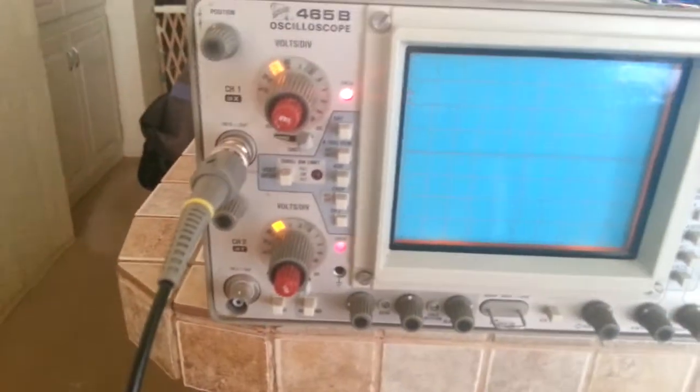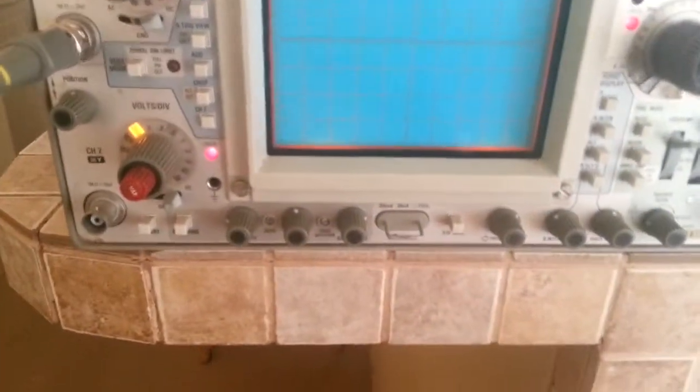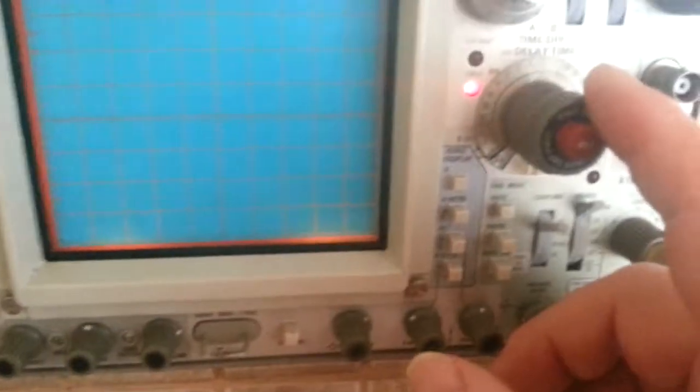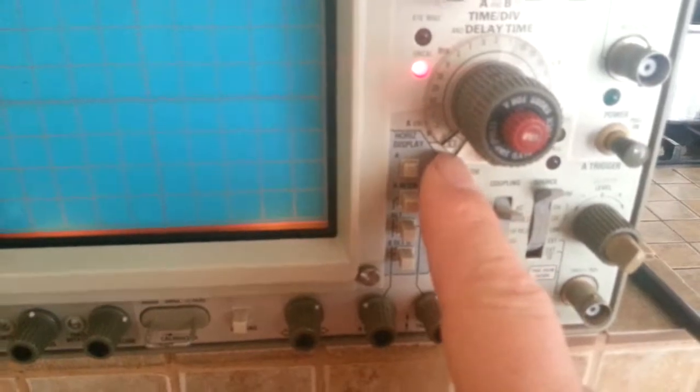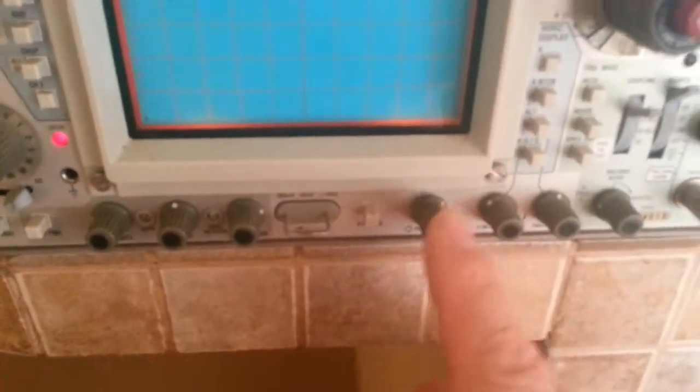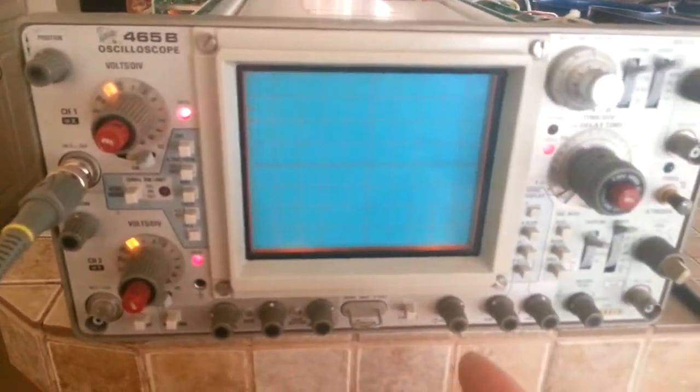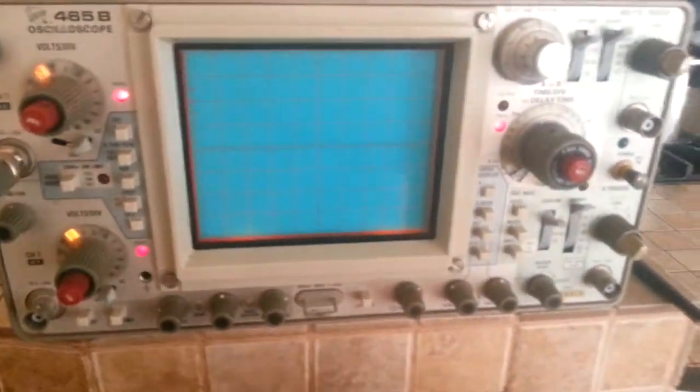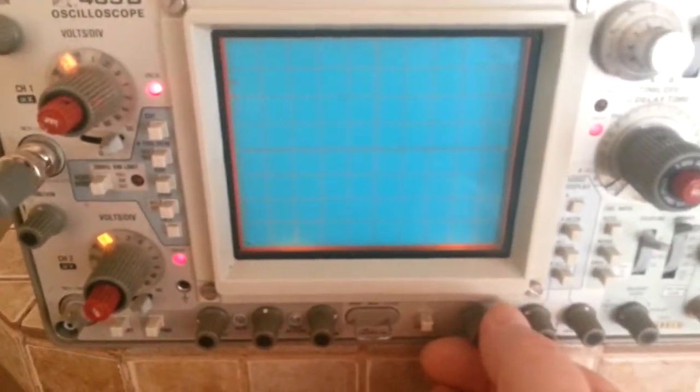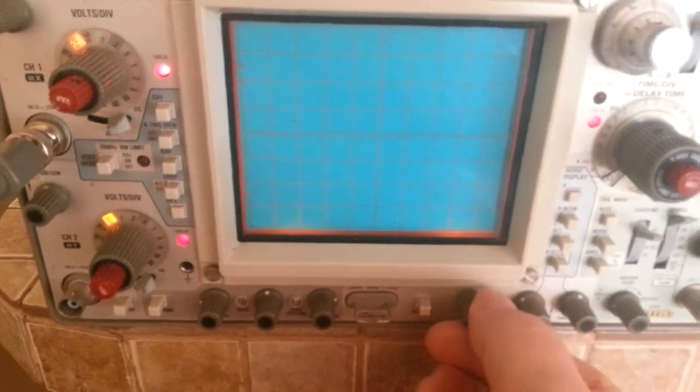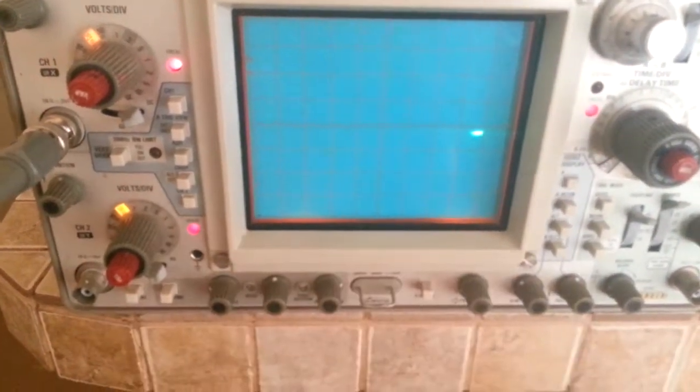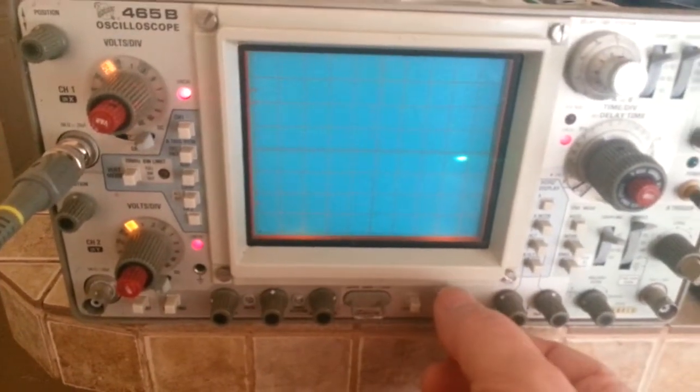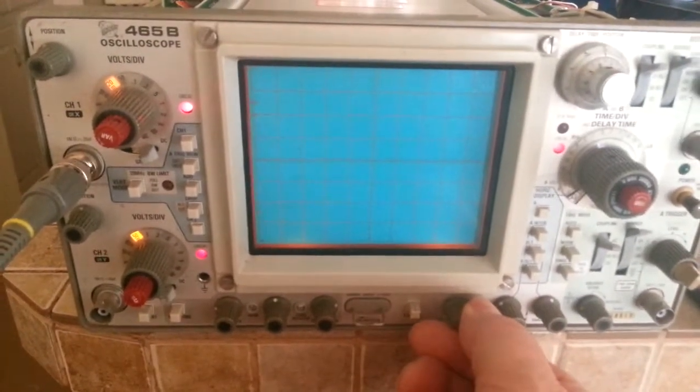Right now the time delay is set for XY mode, and my position knob is essentially halfway. I've got nothing on the screen. Now if I turn the position knob counterclockwise, or to the left, you'll see I've got a dot on the screen. If I turn it back to center, it goes away.